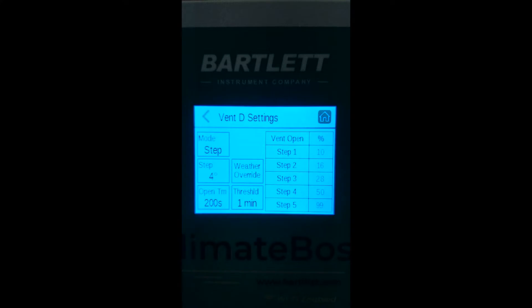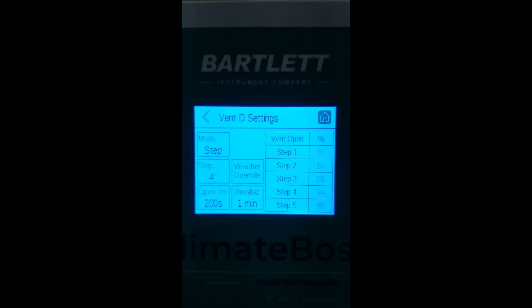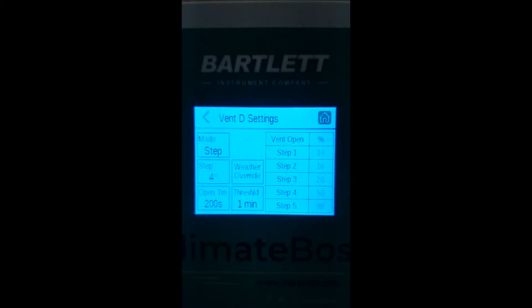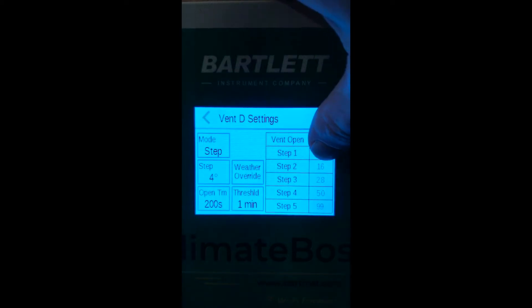In the five step mode, the vent uses each of the manually configured open percentages and the step size to determine how far to open the vent. For example: the set point is 77 degrees Fahrenheit and the step size is 4 degrees Fahrenheit. Therefore, if the temperature rises to 81 degrees, the vent will open to step one, or 10 percent. If it rises four more degrees, it will go to step two, 16 percent.